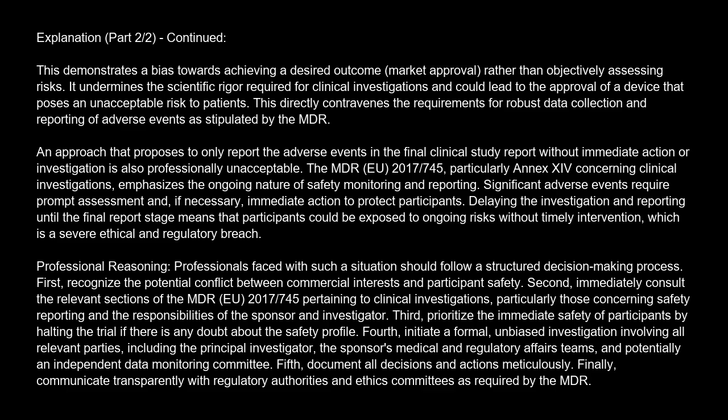An approach that proposes to only report the adverse events in the final clinical study report without immediate action or investigation is also professionally unacceptable. The MDR EU 2017/745, particularly Annex XIV concerning clinical investigations, emphasizes the ongoing nature of safety monitoring and reporting. Significant adverse events require prompt assessment and, if necessary, immediate action to protect participants. Delaying the investigation and reporting until the final report stage means that participants could be exposed to ongoing risks without timely intervention, which is a severe ethical and regulatory breach.